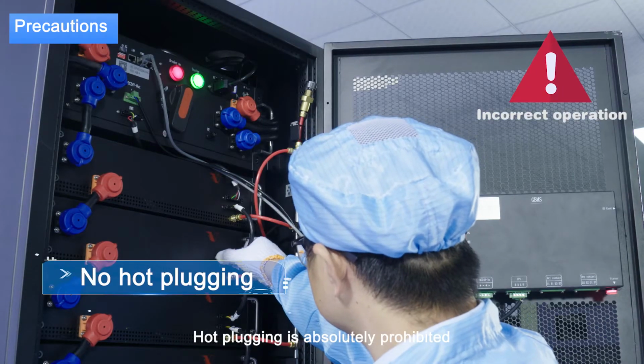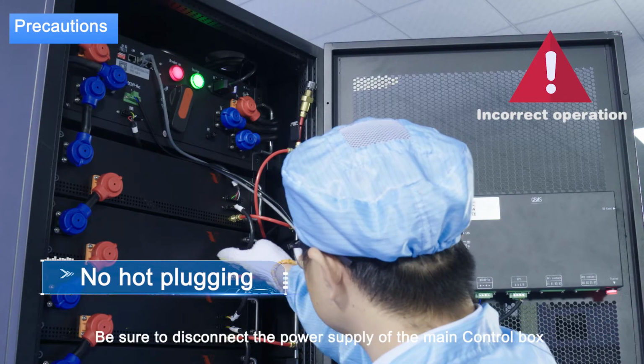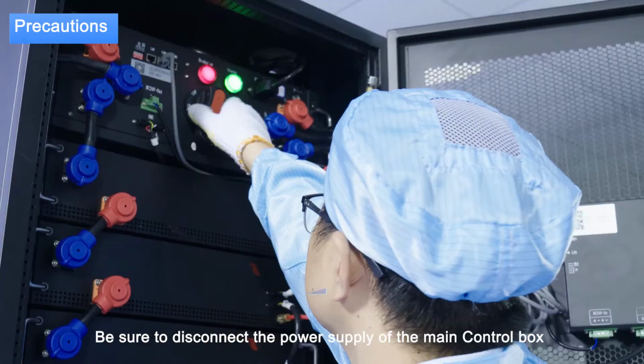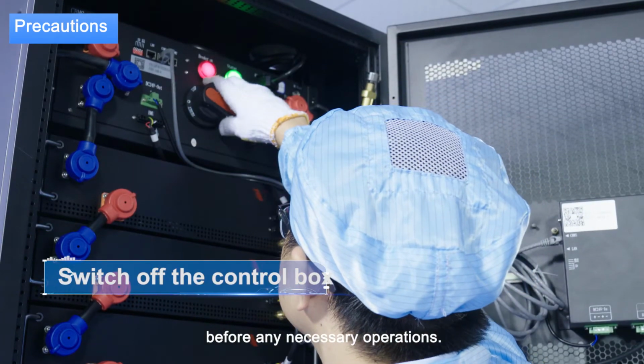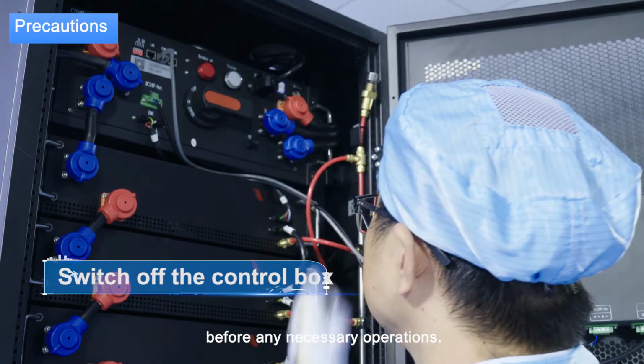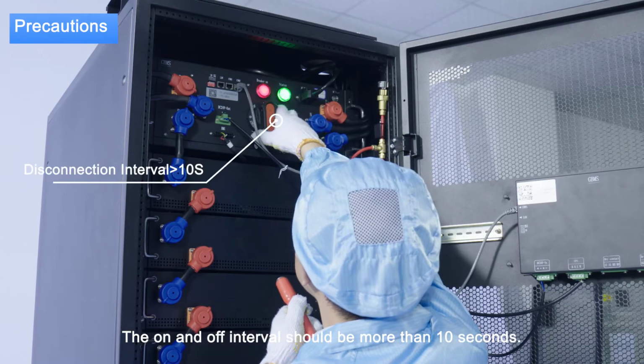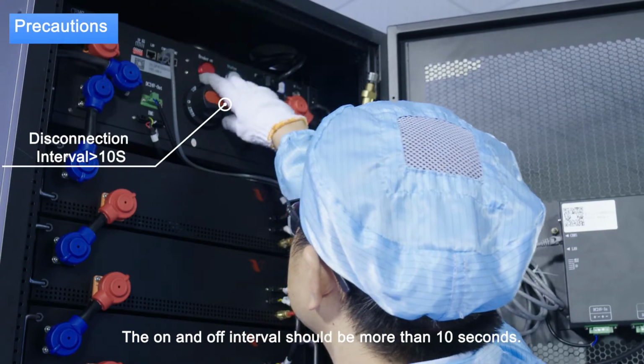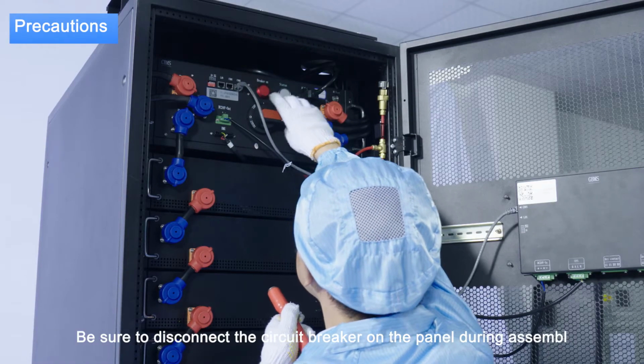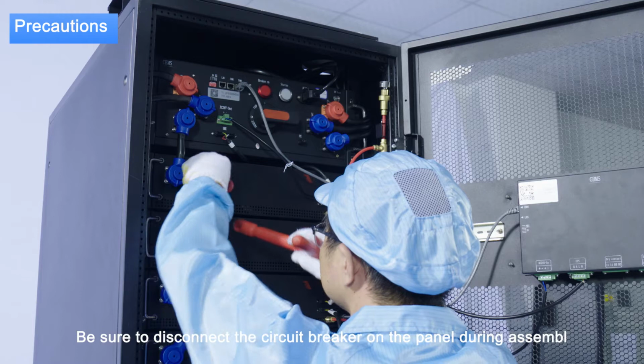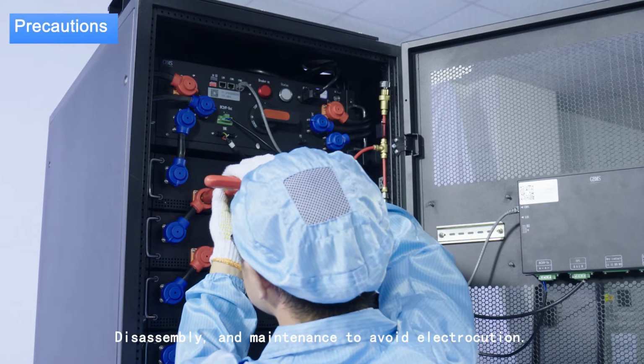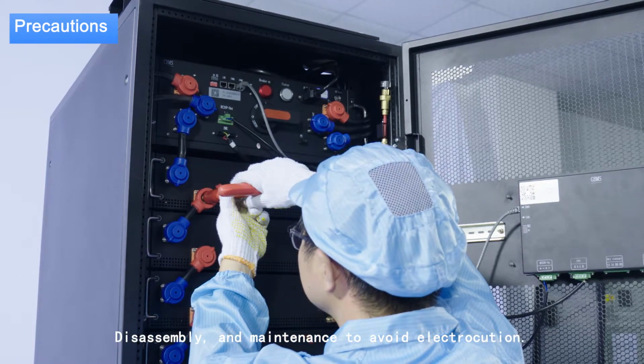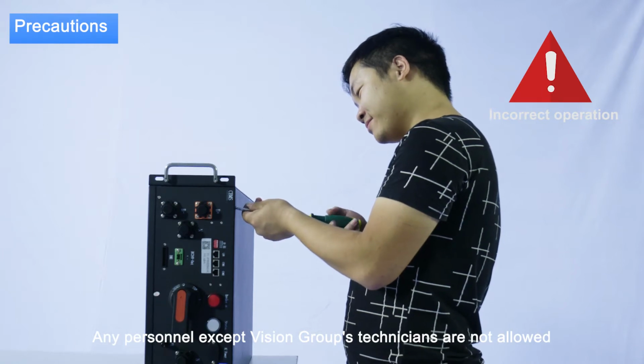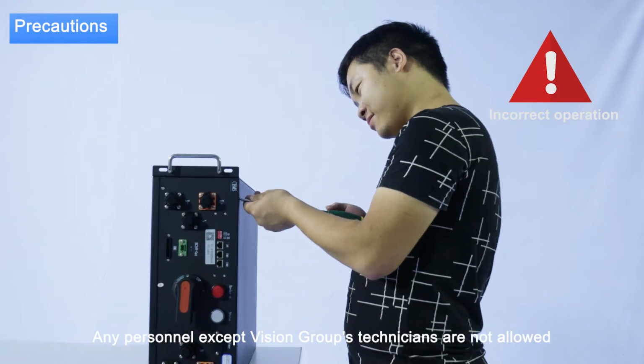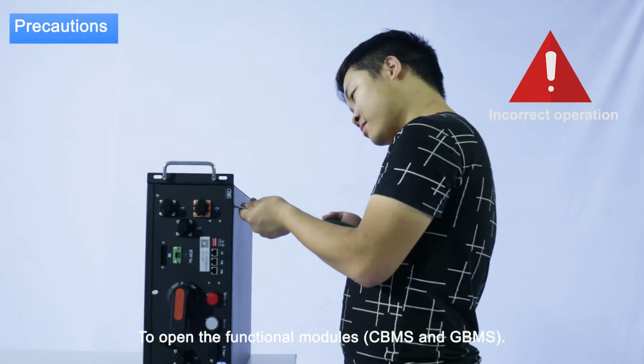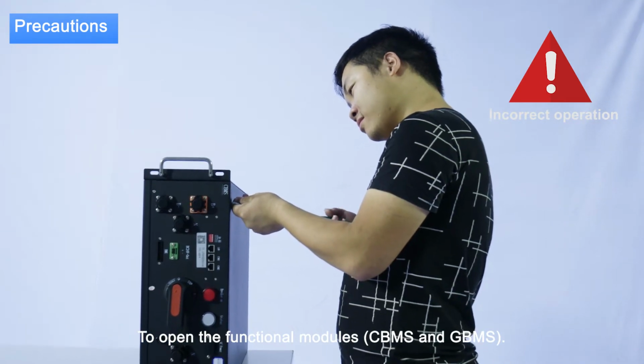6. Hot plug-in is absolutely prohibited. Be sure to disconnect the power supply of the main control box before any necessary operations. 7. The on and off interval should be more than 10 seconds. 8. Be sure to disconnect the circuit breaker on the panel during assembly, disassembly, and maintenance to avoid electrocution. 9. Except for Vision Group's technicians, no one is allowed to open the functional modules, CBMS and GBMS.